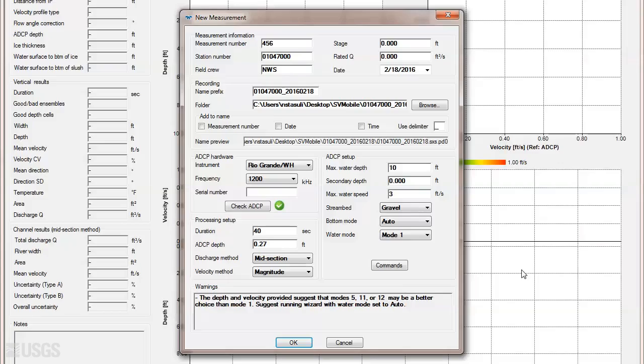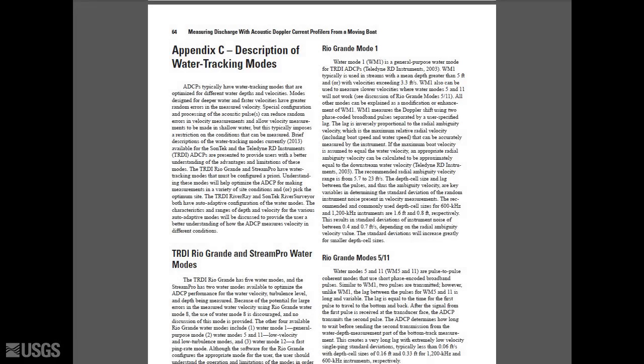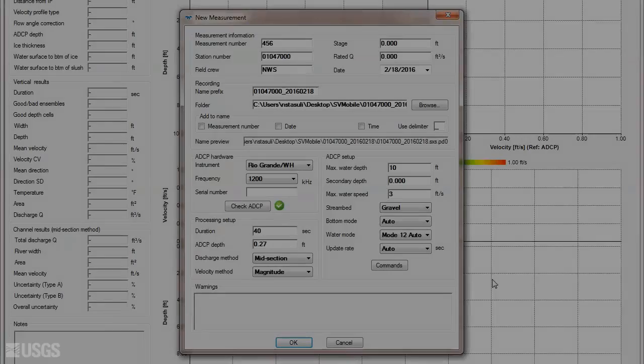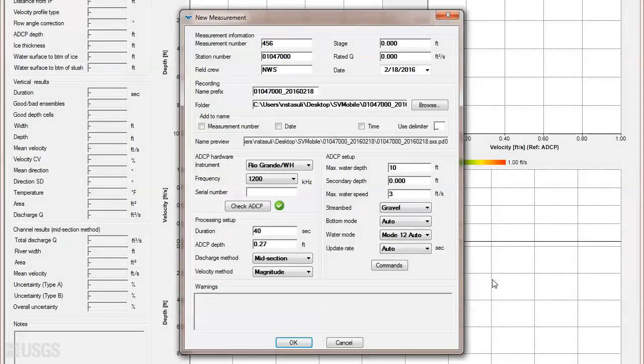The bottom mode is typically left to auto, while the water mode must be selected manually. For more information on these modes and the modes available for other ADCPs we will discuss, review USGS T&M 3A22 Appendix C. To preview the commands based on your selections, you can click the Commands button here.